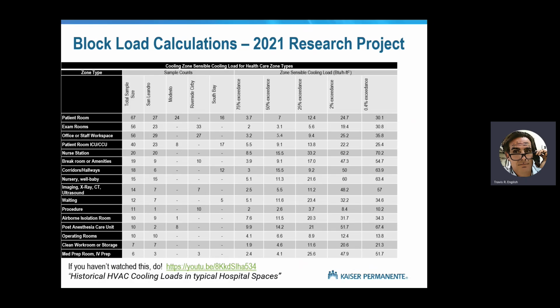And we did publish this paper through ASHRAE with the peer review and all that. So you could buy it from ASHRAE. You don't need to. You go to YouTube and you type in historical HVAC cooling loads in typical hospital spaces, and it'll pop up. More than anything else, I want to communicate that this is possible. So our point in publishing this wasn't so much to say, hey, these are the historical loads, use them, although that is true. But the real point here is that with cloud-based diagnostic systems, we can look at historical loads in any building, any day, any year, and we should be doing that. We should be doing that every day, really.